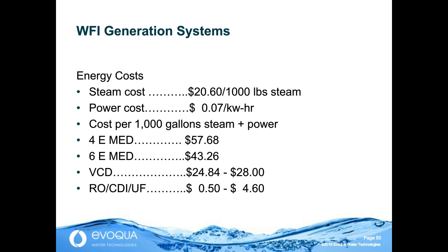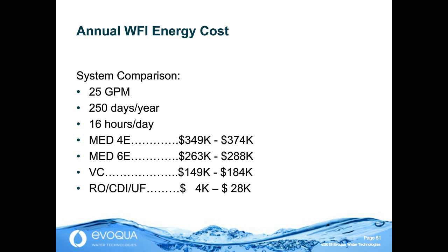So if we look at an annual cost example, 25 gallon a minute WFI production, 250 days a year, 16 hours a day, we see a 4 effect still could be as high as 374,000 a year. A 6 effect is going to reduce it. Vapor compression is going to be even lower, but a membrane system can be far lower and not only be a lower capital cost to begin with, but offer tremendous operating cost advantages.